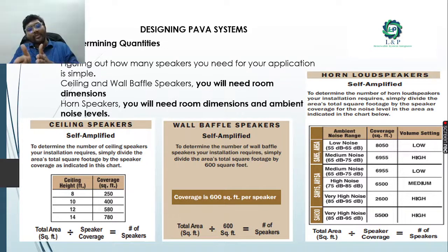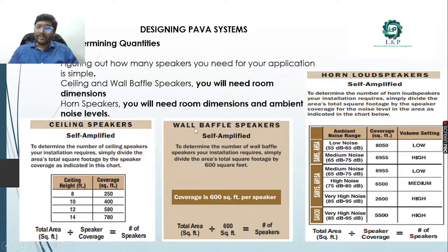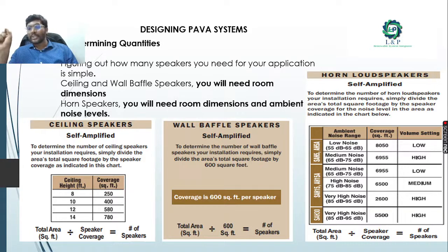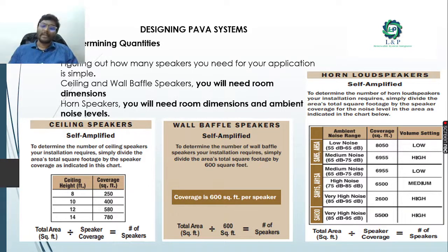For wall baffle speakers, divide the total square footage by 600 to get the number of speakers. For horn loudspeakers, you must also know ambient noise levels in addition to coverage area. The same principle applies: know total area and speaker coverage to find the number required. This method helps determine the quantities of speakers needed to design a PAVA system.